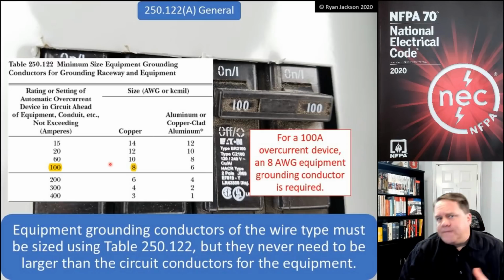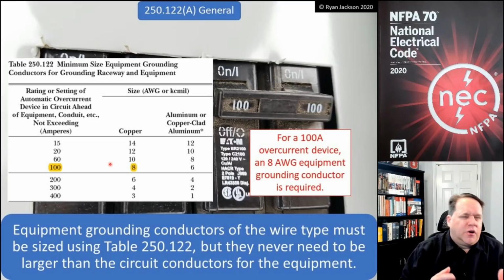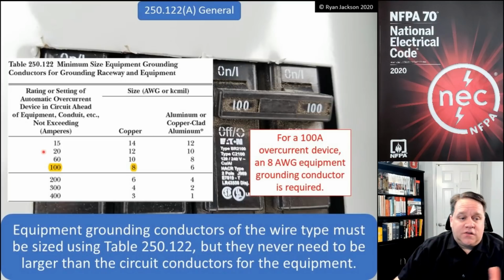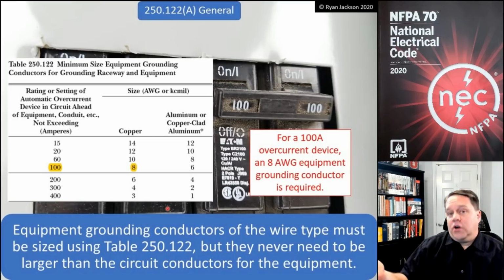And that's a fairly simple concept. The bigger the breaker, the bigger the wire. And I say breaker, but breaker or fuse, same concept. So 250.122(A) just says, listen, nice and easy. Figure out what size of breaker or fuse supplies the circuit, use the table, pull that size wire in your conduit, and you're good to go, right?